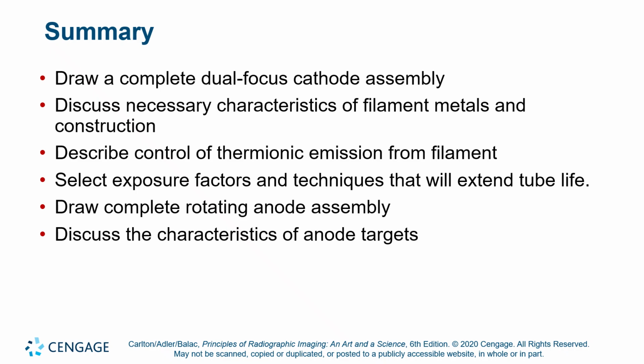We again talked a little bit about how damage manifests in the X-ray machine. Rotor bearing warp, pitting or cracking of the anode, and off-focus radiation and arcing, and then you compromise the vacuum. We talked about what was necessary for X-ray production. That is a source of electrons, a target for them to slam into, and kilovoltage to accelerate them into the target. All the other components, the focusing cup, the beveled anode, the rotating anode, those are all efficiency improvements. The total vacuum is an efficiency improvement. So by an efficiency improvement, that means you can still make a crude X-ray tube.